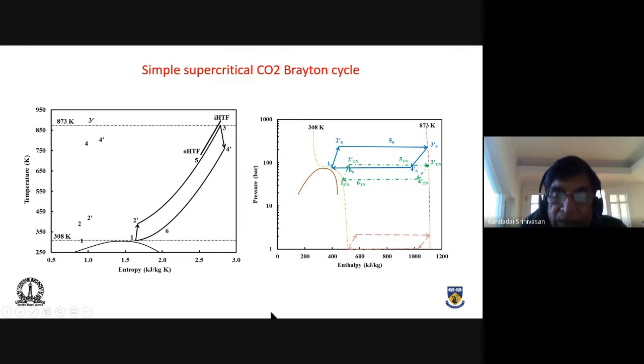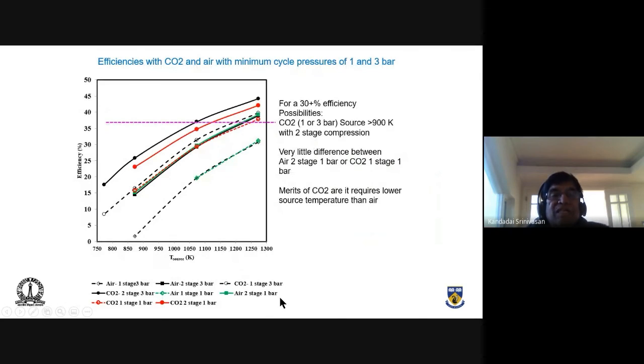This is completely supercritical operation. Now, what type of efficiency are we looking at with a very ideal case, with air and minimum cycle operating pressure of 1 or 3 bar, for 30 plus percent efficiency? That's exactly what we want, since I can already get this kind of efficiency with a modern steam plant. Why should I go and buy a Brayton cycle operating with carbon dioxide when steam is quite efficient? So to sell yourself, first and foremost you have to match the efficiency of the steam cycle. That's why I've drawn a purple line showing the efficiency we're looking at, which is where I'll actually be happy.